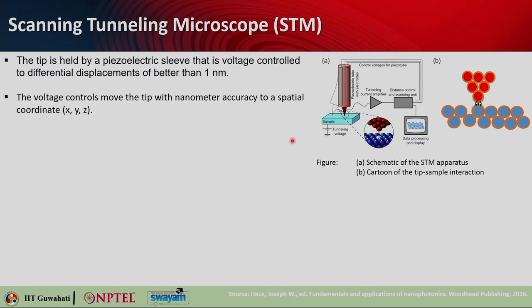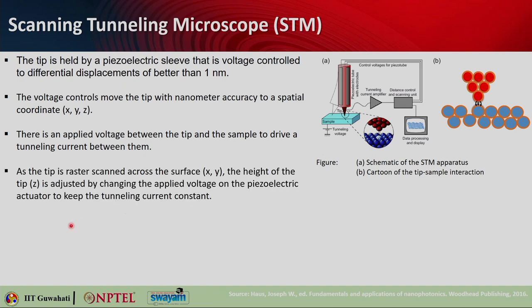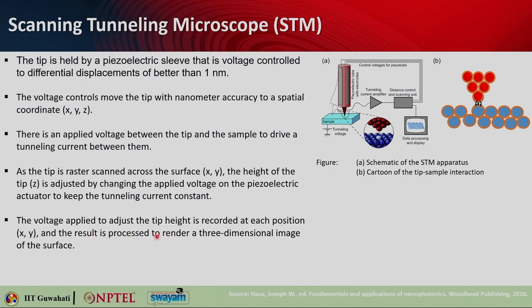In the STM setup, there is a piezoelectric tube with electrodes holding the tip, scanning the sample. The tip is held by a piezoelectric sleeve with voltage control to differential displacement of better than one nanometer, allowing nanometer accuracy in x, y, z coordinates. An applied voltage between tip and sample drives the tunneling current. As the tip is raster scanned across the surface in x, y, the height z of the tip is adjusted by changing the voltage on the piezoelectric actuator to keep the tunneling current constant. The recorded voltage adjustment at each x, y position gives the height, producing a 3D image of the surface.